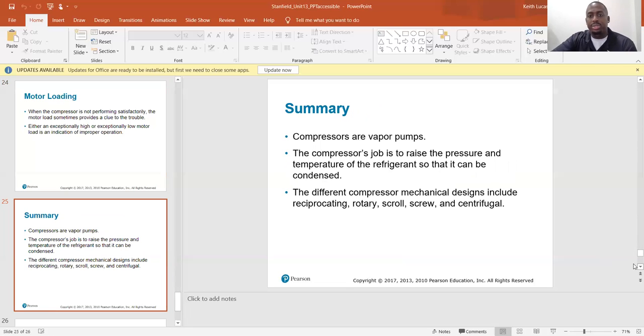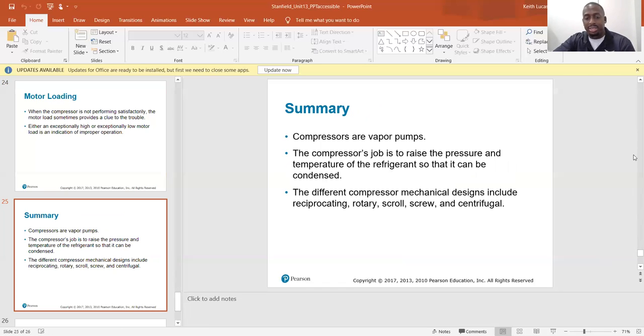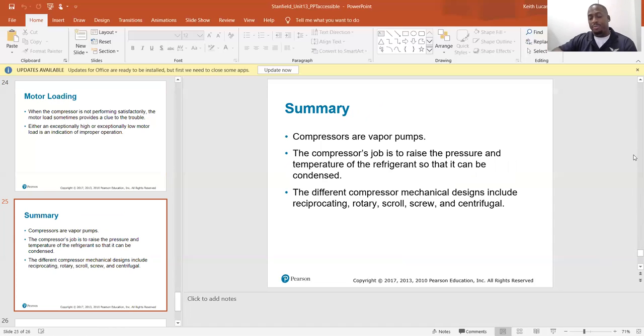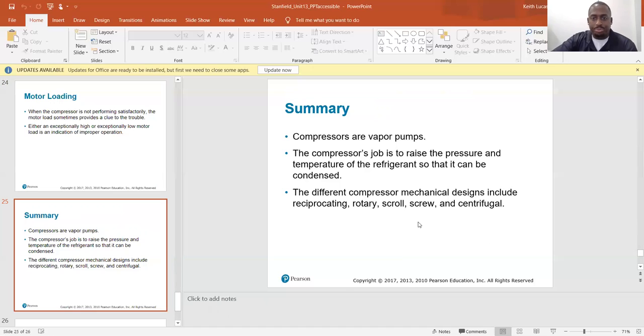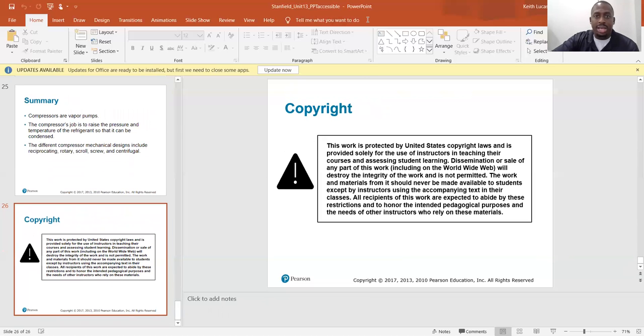In summary: compressors are vapor pumps, absolutely not liquid pumps. The compressor's job is to raise the pressure and temperature of the refrigerant so it can be condensed — we use outside air to condense the refrigerant back to a liquid, so we need to raise the refrigerant temperature and pressure in the condenser at least 20–30 degrees above outside air temperature. The different compressor mechanical designs include reciprocating, rotary, scroll, screw, and centrifugal. That's it for unit 13 — read your book for more info.